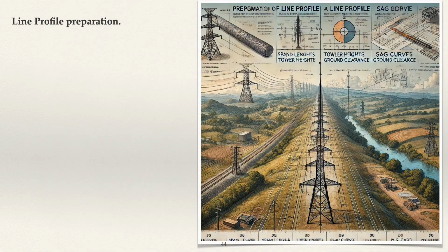Profile preparation. The profile provides a visual representation of the transmission line's path, showing towers, conductors, sag, and terrain. It highlights critical points where extra clearance or adjustments in tower height may be required. Alongside the profile, the team develops a tower spotting plan, detailing the positioning of each tower along the route, specifying type, height, and foundation requirements. Optimize spacing between towers to balance structural integrity and cost effectiveness. Weight spans are calculated to ensure stability, especially in regions with uneven terrain or crossings.